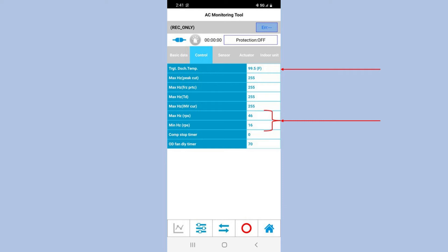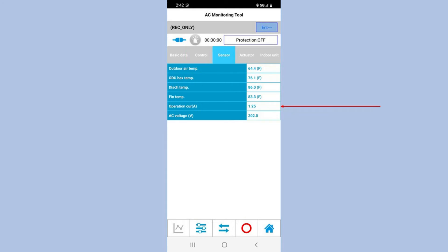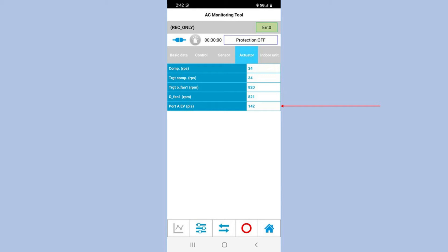The operating current shown on the screen is the one that it's reading internally and it may not match your amp clamp, but it will be the one it's using to control the compressor speed. If the amps get too high, again, this is the one the computer is using. EV pulses will also appear on the screen. Remember from class, 470 to 480 pulses is fully opening depending on the unit. Now we usually expect near 50 percent, even up to 70 percent is considered normal. You'll see here it's pretty low, probably down to 20 some percent, but the unit's just started up, it hasn't adjusted yet.